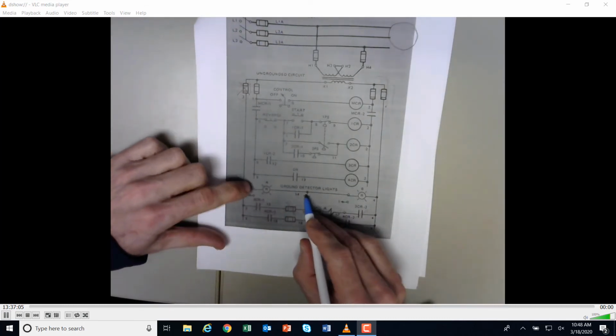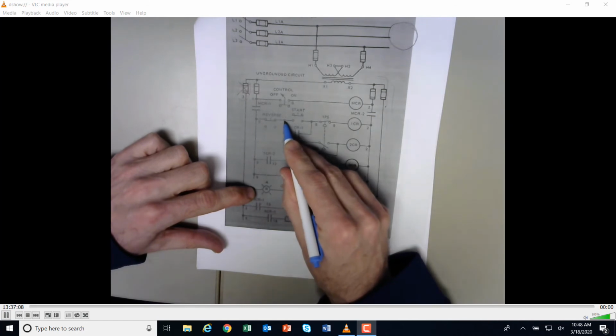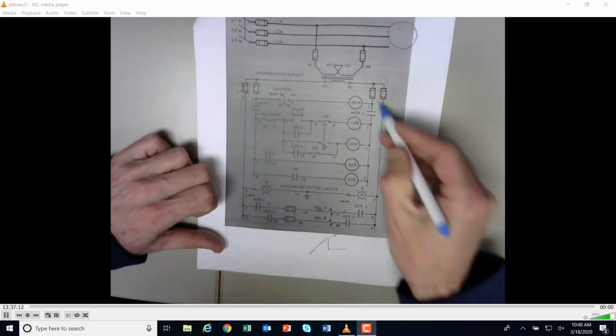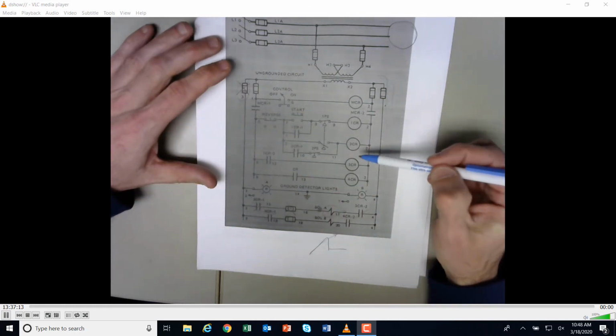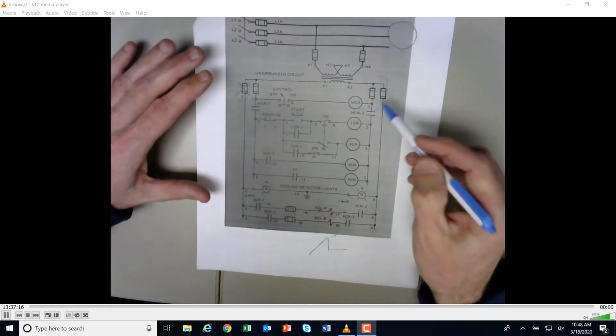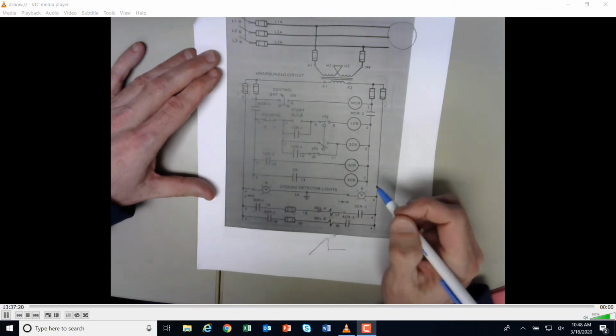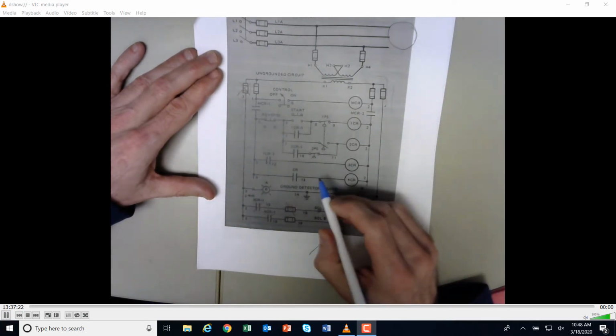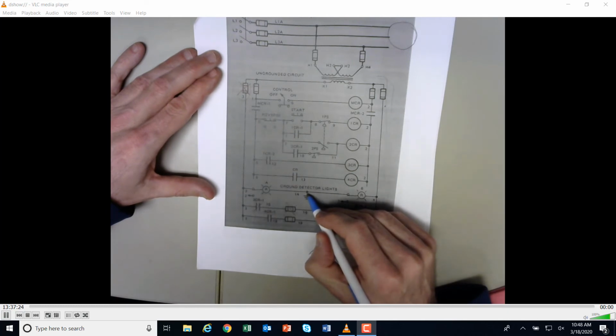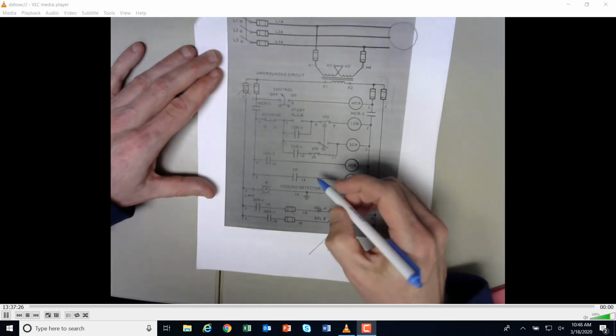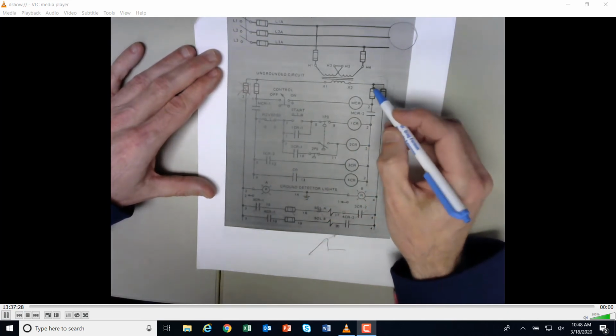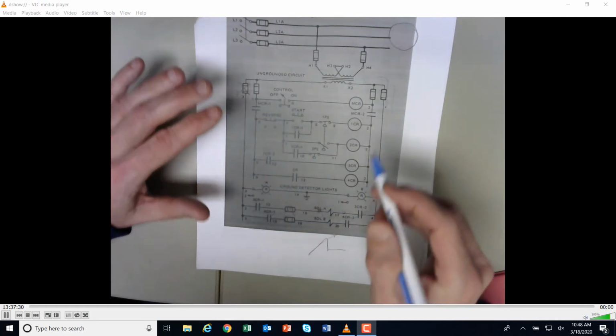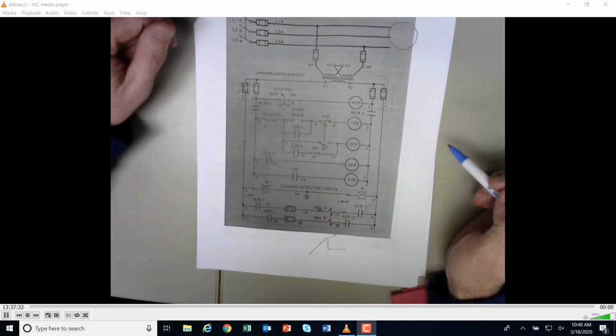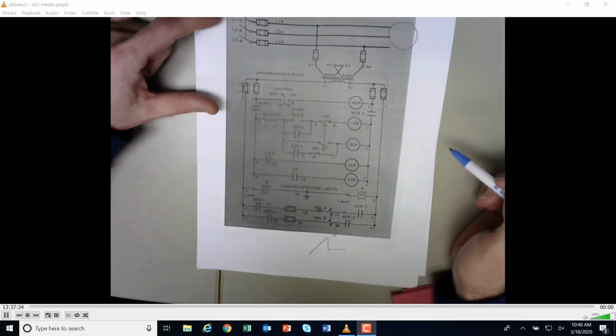So if we were to get a ground fault, or something touched metal and it touched the entire control panel here, well, there's no earth, this panel is looking just at itself, and therefore you're not going to blow a fuse, because instead of just having one short circuit that would blow this, you would need two. You'd have to get to either side of this transformer, if that makes sense.